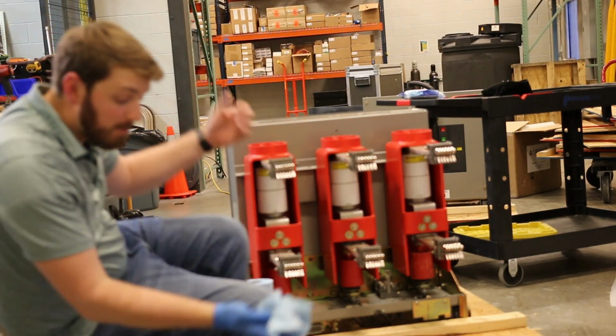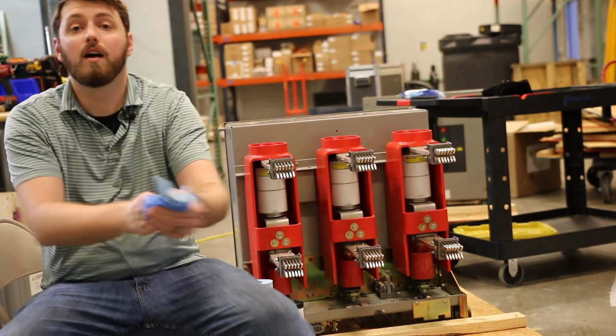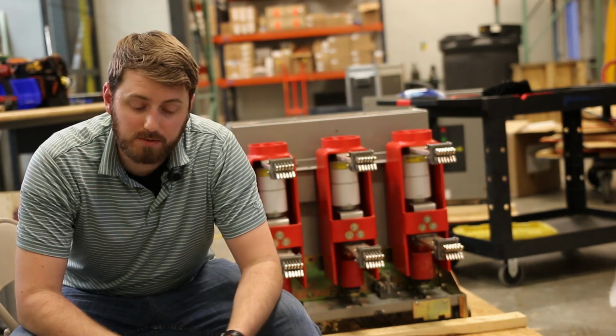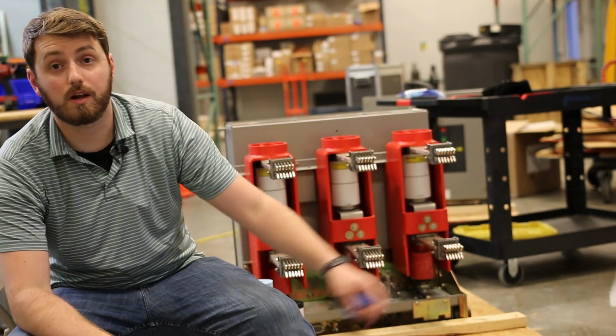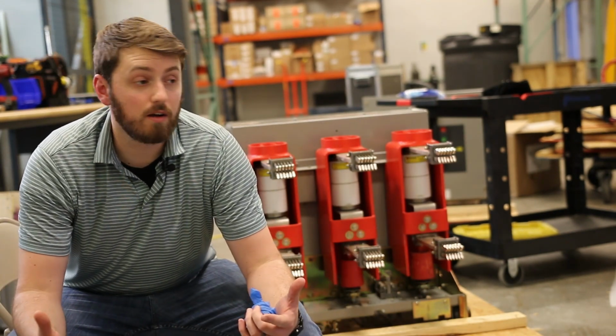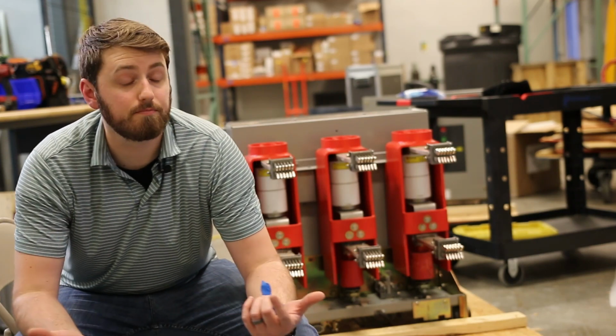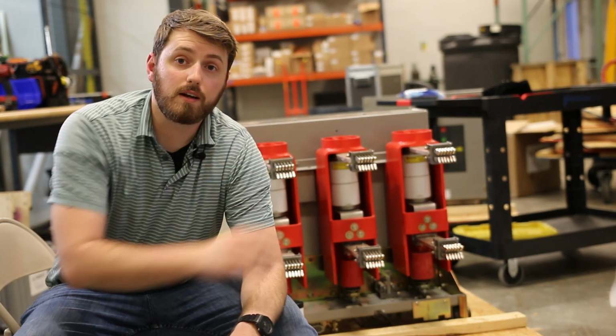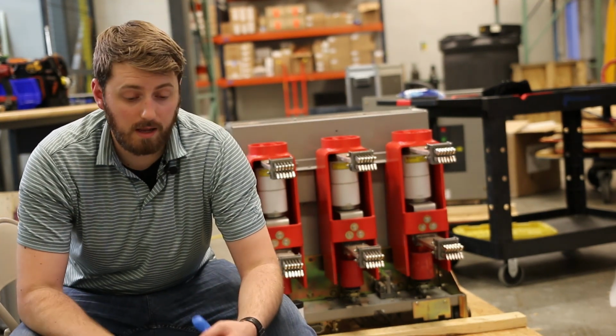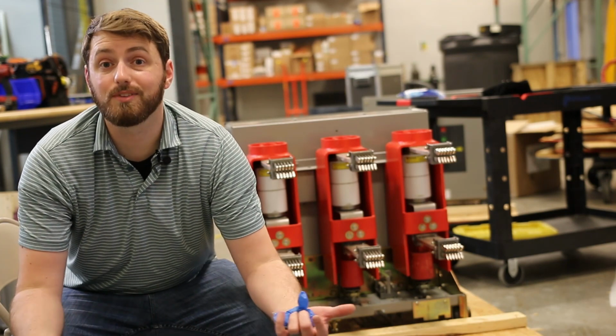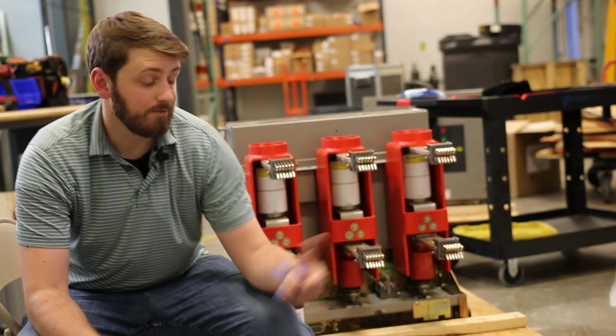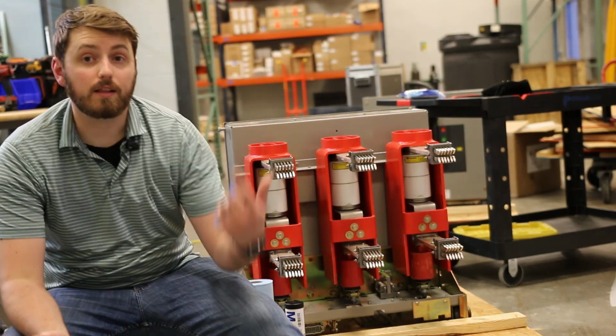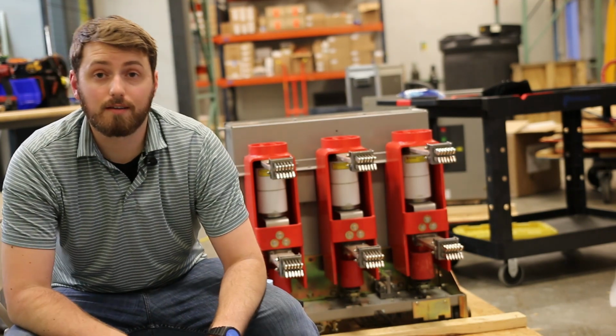And that's it, gentlemen. We have tested a medium voltage vacuum circuit breaker. This 1200 amp VR is a really good example of ones that are really common in switchgear, heavy industry, even large utilities. This is gonna be very, very typical of what you're gonna see. Eaton, ABB, Siemens, they all make roughly the same thing. They look a little bit different, but the tests are all the same, the timing. Really, you just need to make sure that you're pinned out correctly. The megger, the high pot, the ductor, it's the same test everywhere you go.